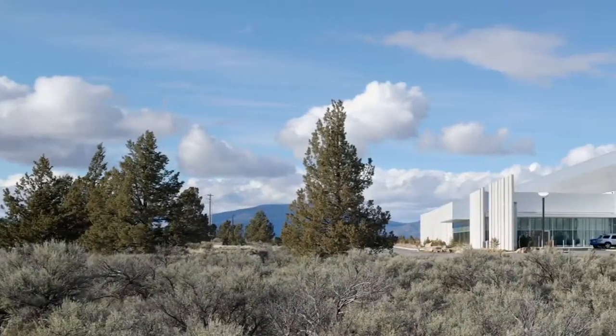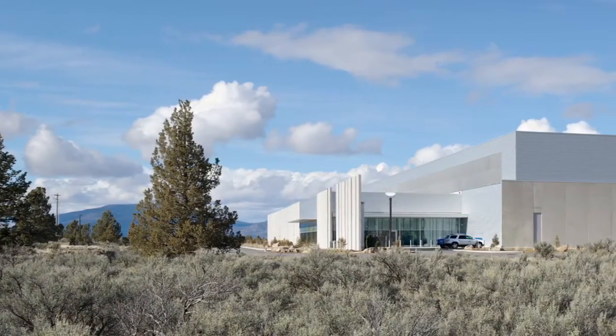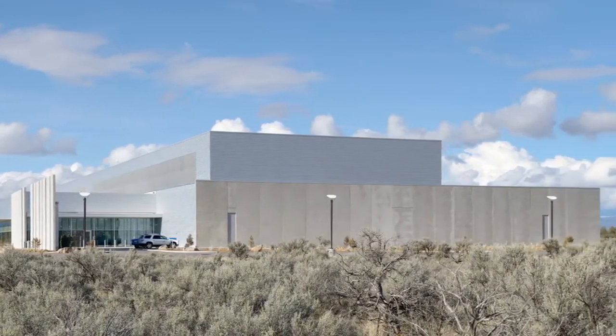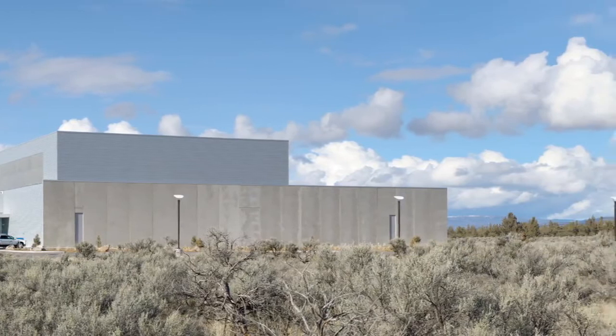Do I need to add moisture to it? How much of the warm air do I add back into it? If it's a really hot day, you don't recirc anything. Generally, you just send it out because it's generally hotter than the air actually coming in, and then all you're doing is cooling. So you don't want the data center to be too cold, because too cold, it's not nice for the technicians, but technically, the air also tends to get dry and you get static electricity, which is not good for the equipment. Makes it difficult to work on.